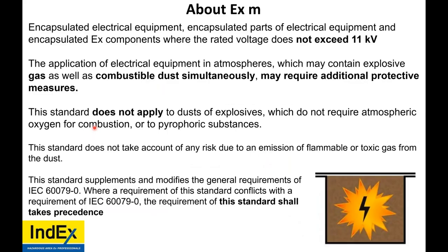Now, let's jump into it. EXM, what is it? Well, it's encapsulated electrical equipment, encapsulated parts of electrical equipment, and encapsulated EX components where the rated voltage does not exceed 11,000 volts. The application of electrical equipment in hazardous atmospheres, which may contain explosive gas or combustible dust, or simultaneously, may require additional protection measures. This standard does not apply to dusts of explosives, which do not require atmospheric oxygen for combustion, or pyrophoric substances. The standard does not take into account any risk due to emission of flammable or toxic gases from dusts, such as a dust being heated, which may produce a gas.